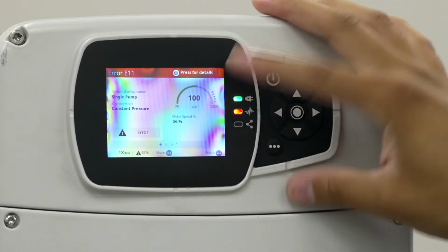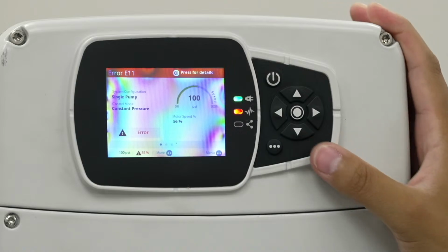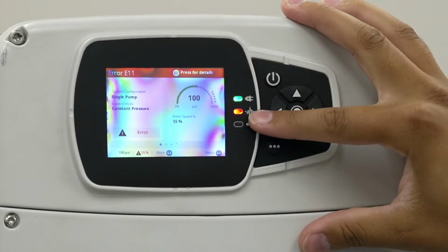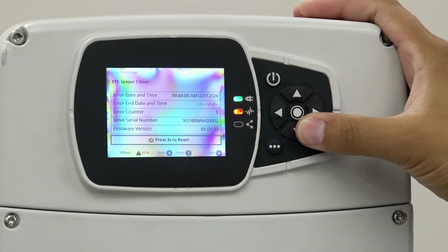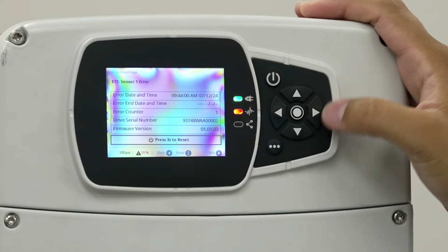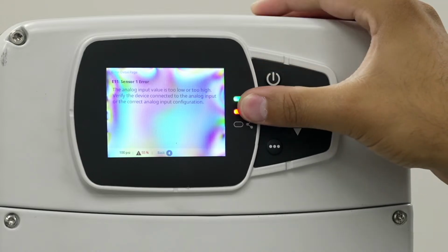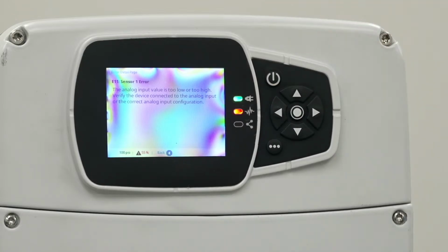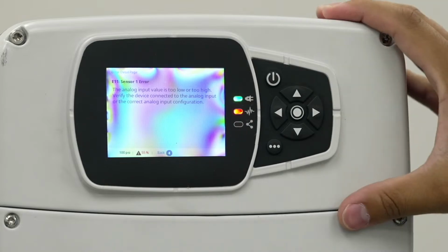This is a demo software, so it is showing, you saw it ramp up to 100 PSI there. And it's still giving us critical system information. Single pump, constant pressure. I'm showing that error, so the red light here is telling me there's an error E11. I can click the enter button, and it's going to give me a date, time. But if I click over for info, it's going to tell me what E11 is. So it's a sensor 1 error. It's not getting an analog input reading from the sensor, which is right. We don't have a transducer wired into this right now. It's expecting to see one, so it's not getting that 4 to 20 milliamp signal. It's seeing 0, so it's letting me know that there's something wrong with my sensor.